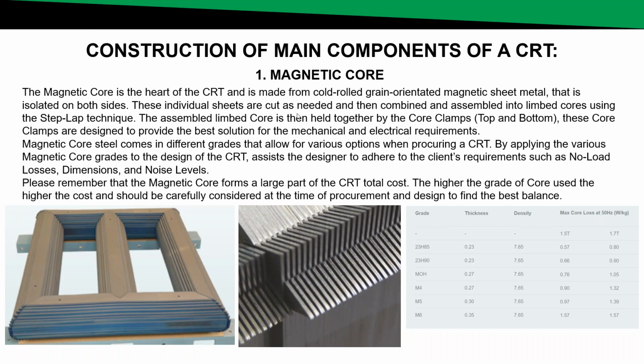The assembled core is held together with core clamps, top and bottom usually. These core clamps are usually designed to provide the best solution for mechanical and electrical requirements. Magnetic cores also come in a big range of classes or types. These classes and types can be used to assist the design engineer to fulfill the requirements of the client, such as no load losses, dimensions, and noise levels.